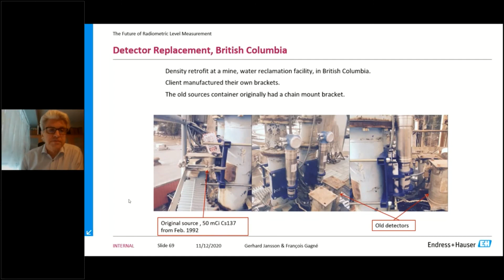That is something that we can do easily. There is usually a mounting bracket provided with each vendor's density gauges. We will just remove the detector, which is typically attached with 4 screws in a square, usually 6.5 or 6, maybe sometimes 7 inches apart. We just have a plate, we put our detector on that, and put that in place of the old detector, and then we can usually start up this operation without any problem.